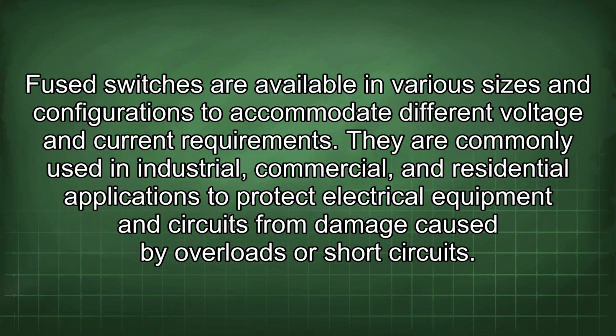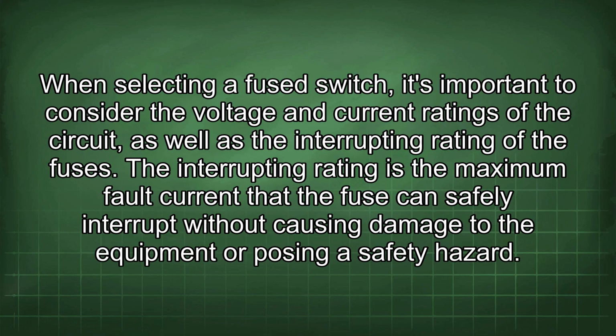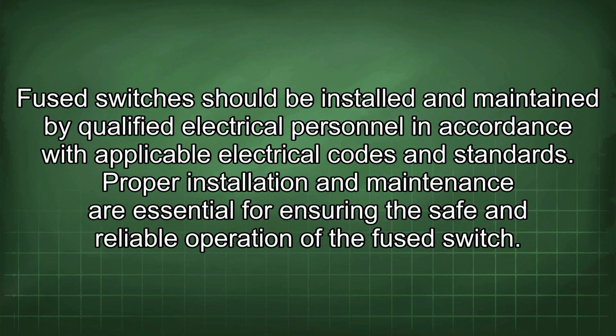Fuse switches are available in various sizes and configurations to accommodate different voltage and current requirements. They are commonly used in industrial, commercial, and residential applications to protect electrical equipment and circuits from damage caused by overloads or short circuits. When selecting a fuse switch, it's important to consider the voltage and current ratings of the circuit, as well as the interrupting rating of the fuses. The interrupting rating is the maximum fault current that the fuse can safely interrupt without causing damage to the equipment or posing a safety hazard. Fuse switches should be installed and maintained by qualified electrical personnel in accordance with applicable electrical codes and standards. Proper installation and maintenance are essential for ensuring the safe and reliable operation of the fuse switch.